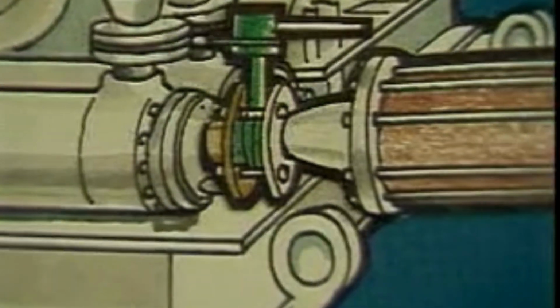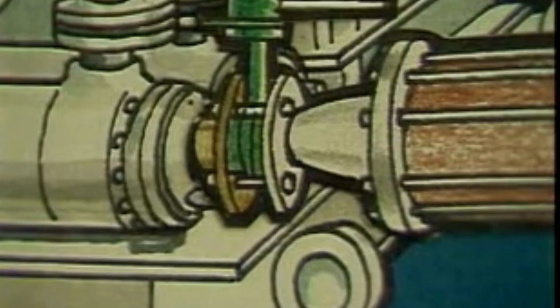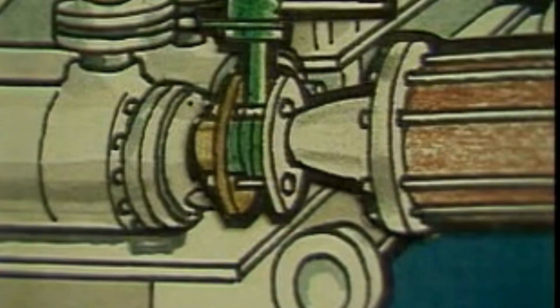How do you install these flow control valves into your system? Well, there's really no special installation technique required to do this job. You see, the water flow direction is marked on the valve, and the piston should face the supply side of that line. If it's installed backwards, it won't control the flow. Be sure to clean the lines upstream of the valve of particles larger than approximately 1/16 of an inch in diameter, which is equivalent to a 20 mesh strainer. This will ensure that the valve won't clog once you start putting a flow through it.